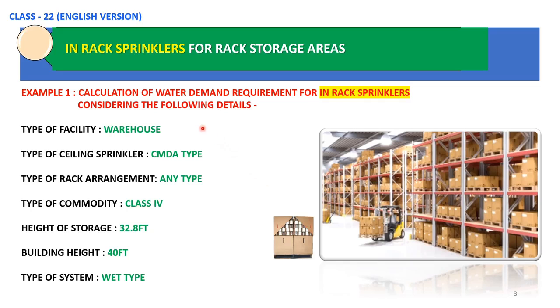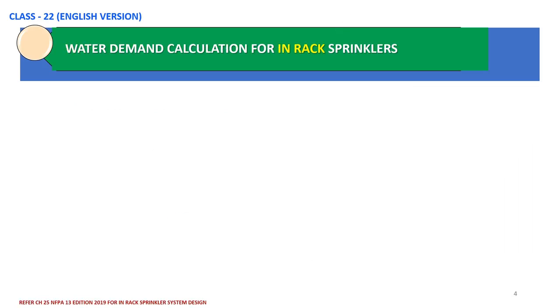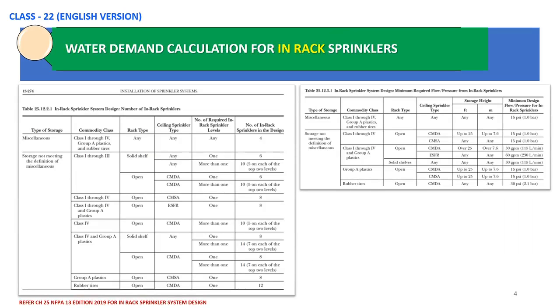Coming back to our example, the type of facility is a warehouse. CMDA type sprinklers are installed here, and rack sprinklers are also installed in this particular warehouse. We are going to calculate the water demand based on storage height and type of commodity classification. There are two tables extracted from NFPA 13 Chapter 25, 2019 edition.